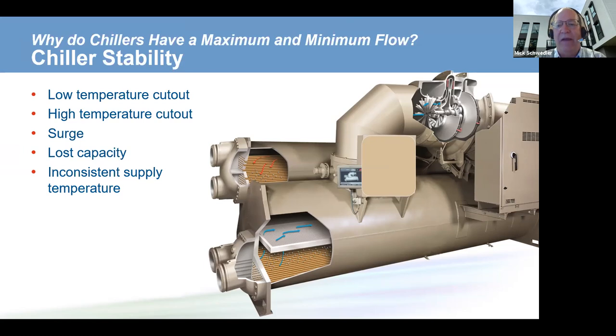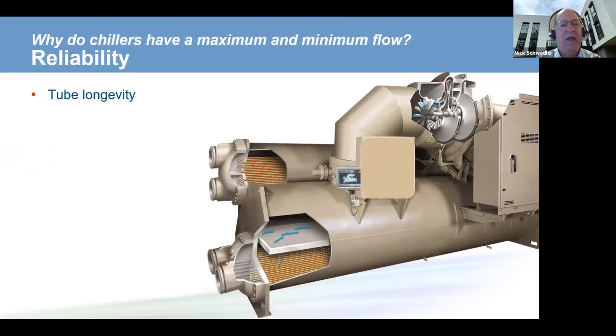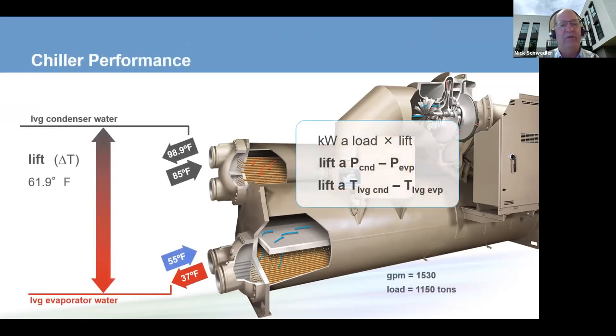We can also lose capacity. And if we go below the minimum evaporator flow rate, we don't have good control of the supply or the chilled water set point for the chiller. How about the maximum flow rate? Well, with a maximum flow rate, if we go above that, we can start to erode the tubes. We erode the tubes, the longevity goes down, the reliability gets worse, and we might have to replace the chiller earlier or retube that chiller. So stay between the minimum and maximum flow rates.